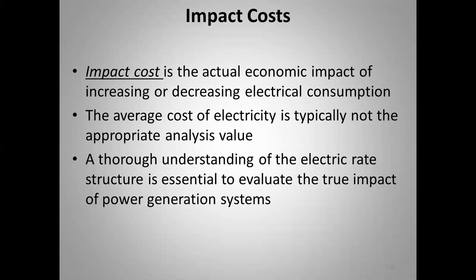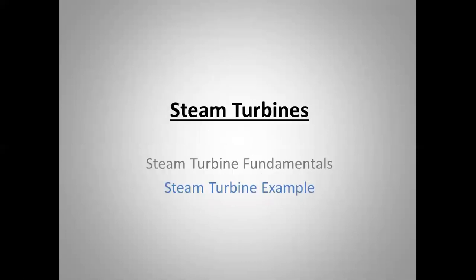Impact cost is defined as the actual economic impact of increasing or decreasing electrical consumption. We don't want to use the average cost — it's that last kilowatt-hour we're saving or adding that determines a project's value. A thorough understanding of the electric rate structure is essential for this analysis.